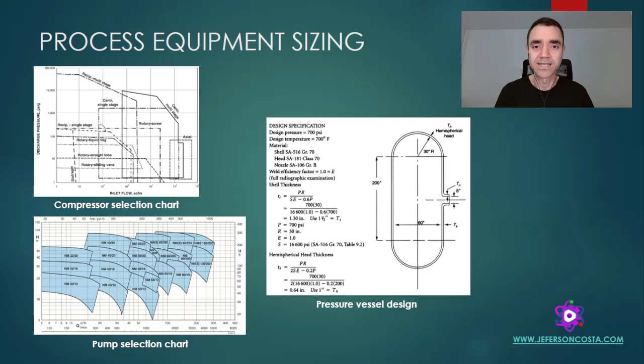And we do that by filling in what are called the process data sheets for equipment, for control valves, for pressure relief devices, etc. With the process flow diagram, heat and material balance, and equipment sizing, not necessarily done in sequence, sometimes in parallel, we are able to develop the piping and instrumentation diagram. So here, in our terminal example, we have the block flow diagram, where the main objective is to define the main units related to this process. After that, we have the process flow diagram, where we can see the main equipment and main controls, and also the material streams associated with each one of these lines.